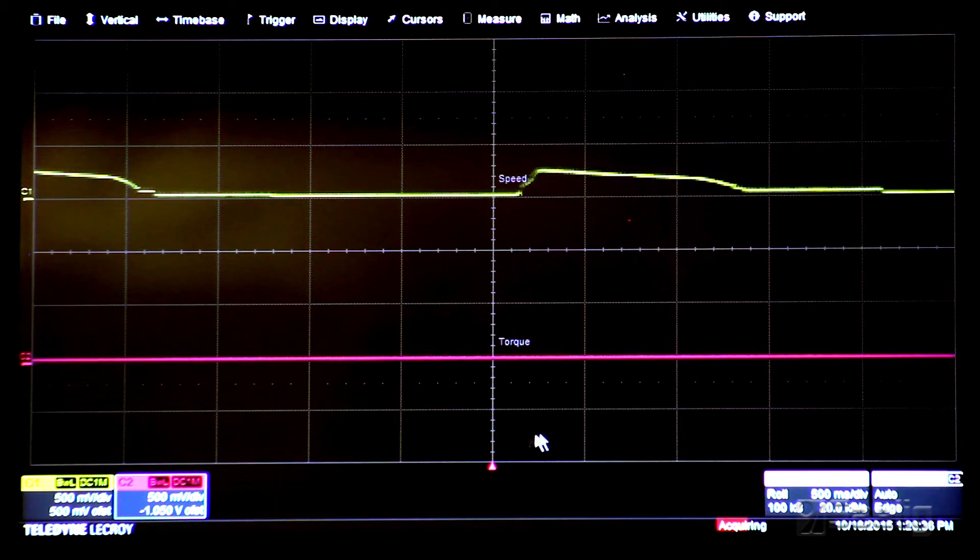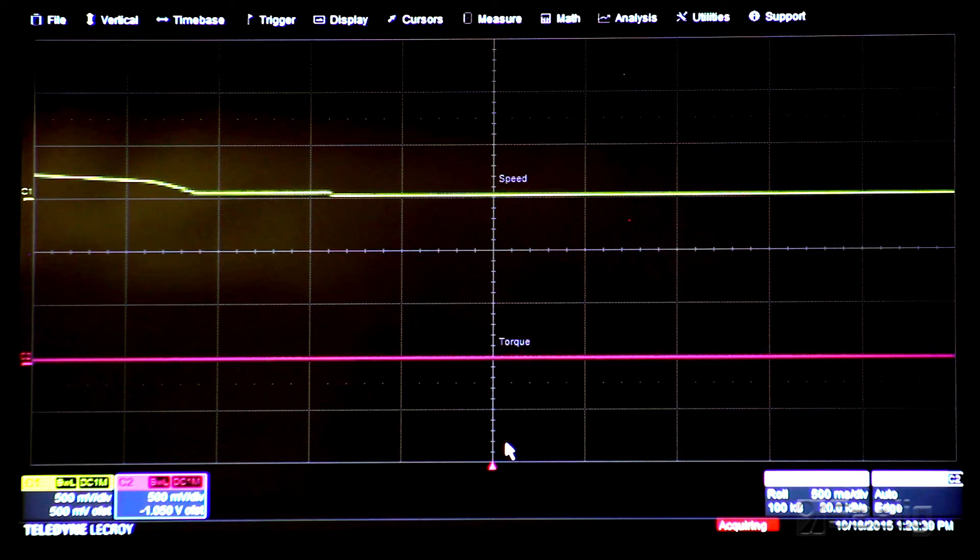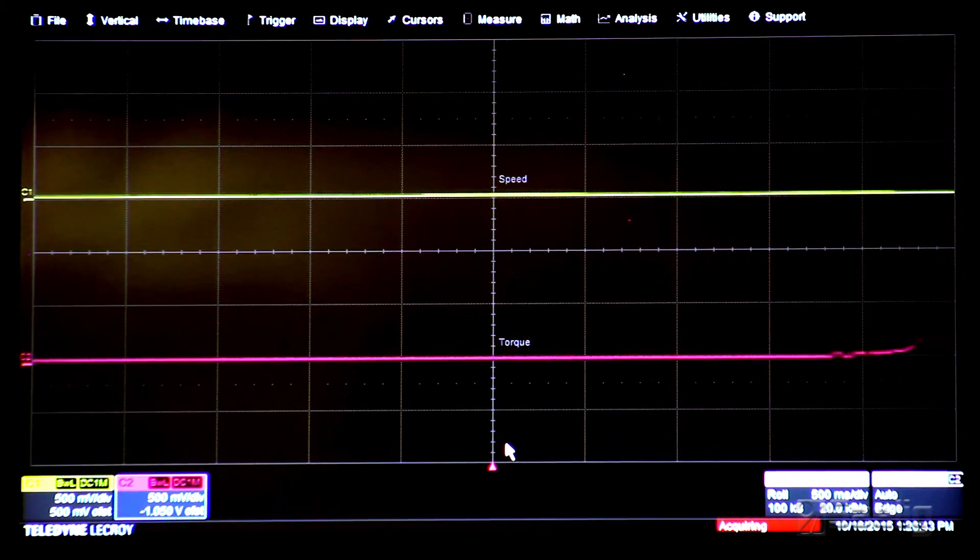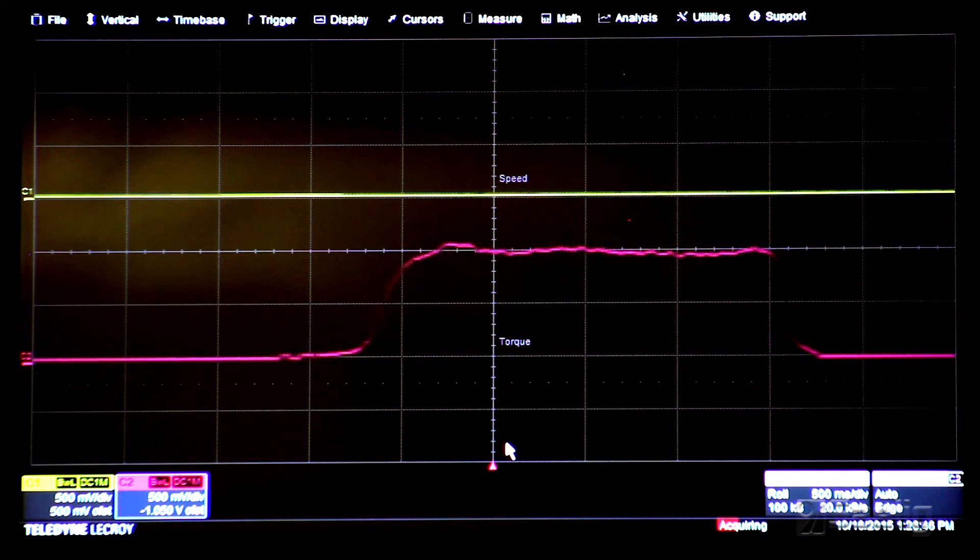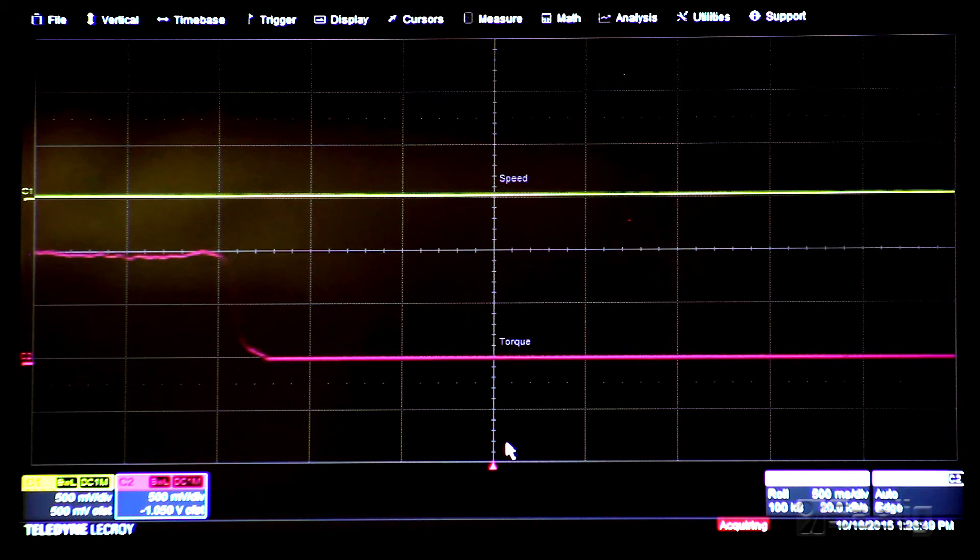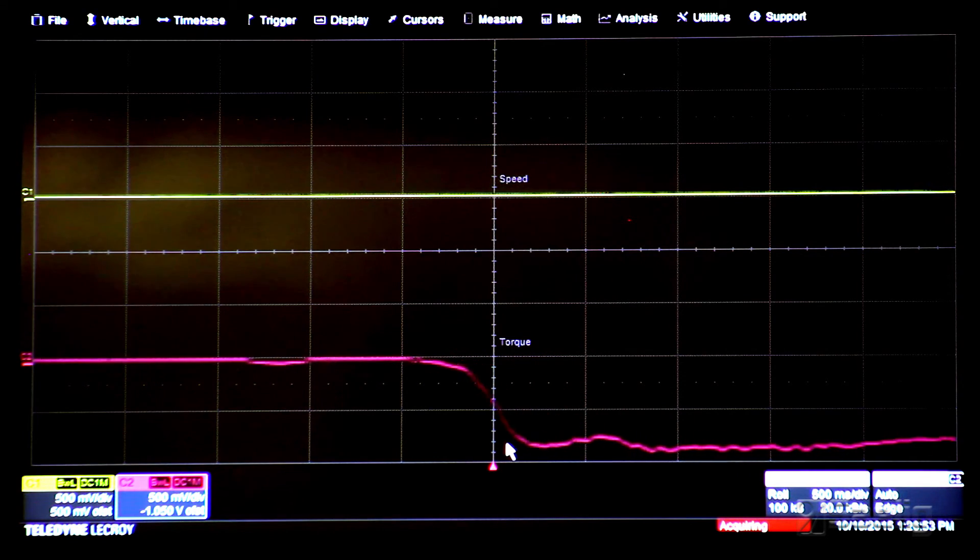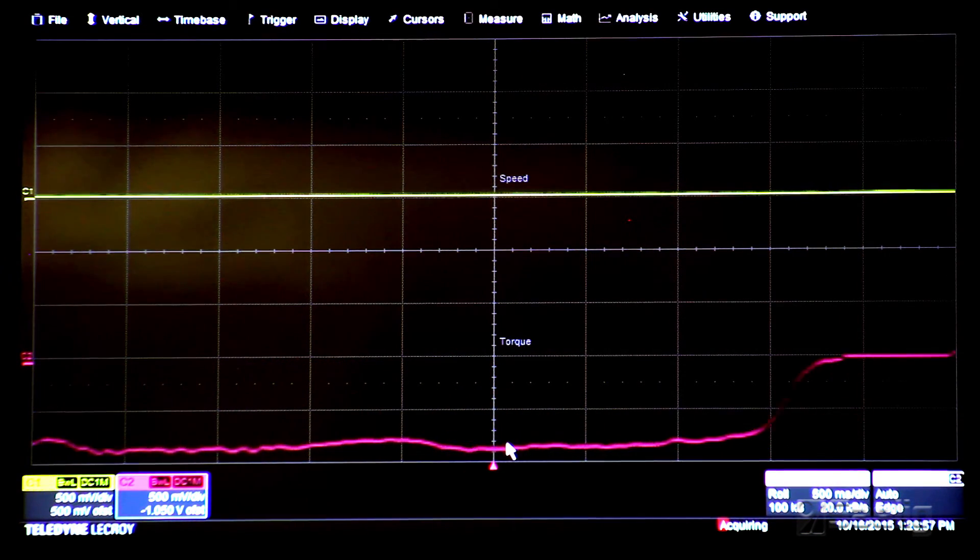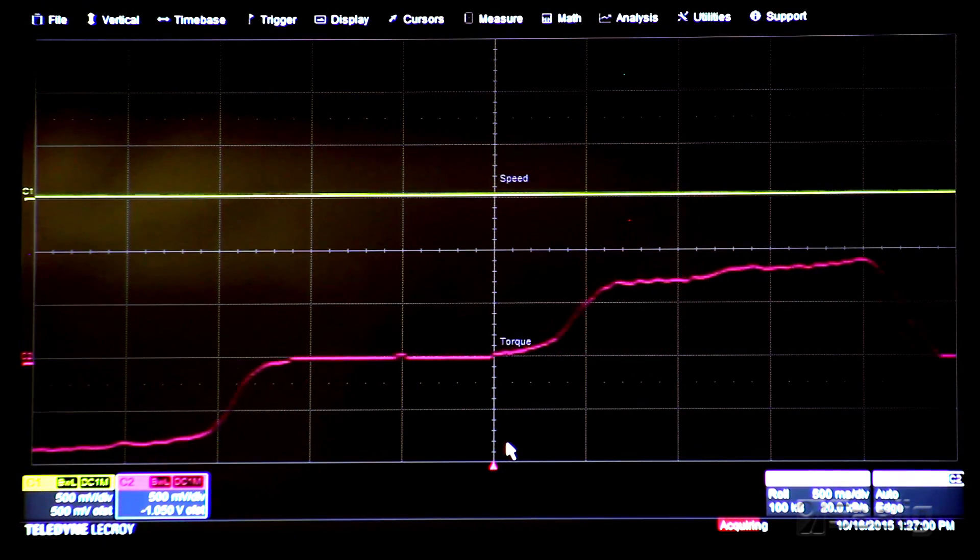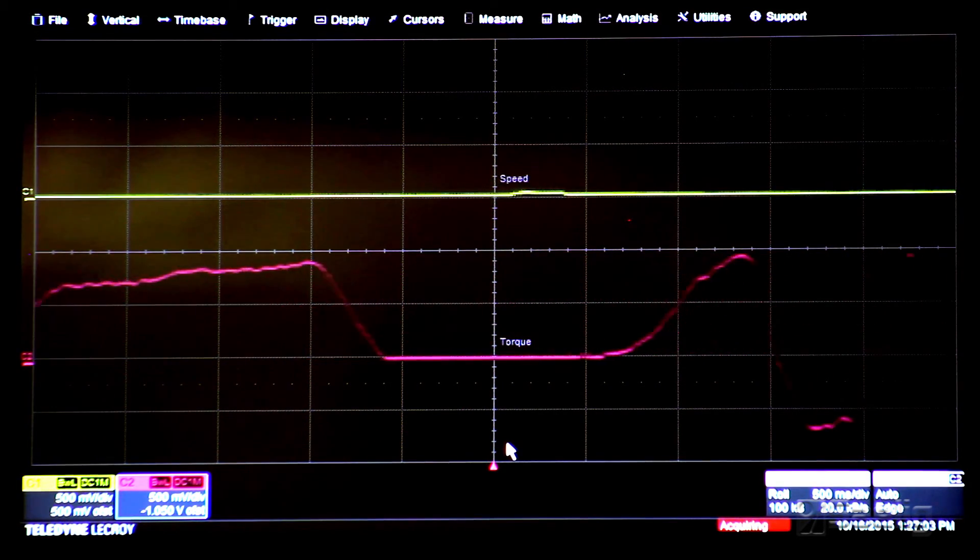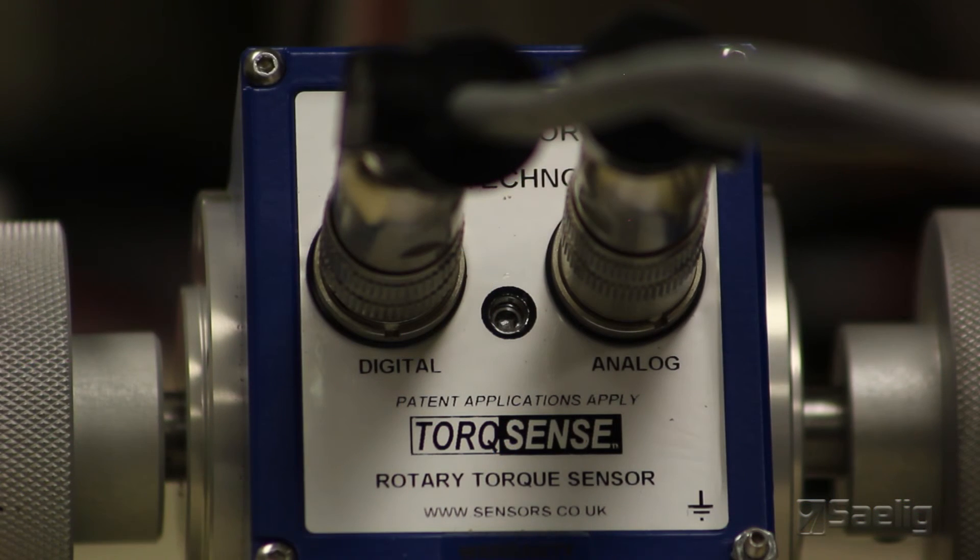I wanted to demonstrate that a clockwise input into the torque transducer results in a positive voltage torque output like this, and a counterclockwise input into the torque transducer results in a negative voltage output like this. And of course, the transducer is useful for both dynamic and static torque measurement.